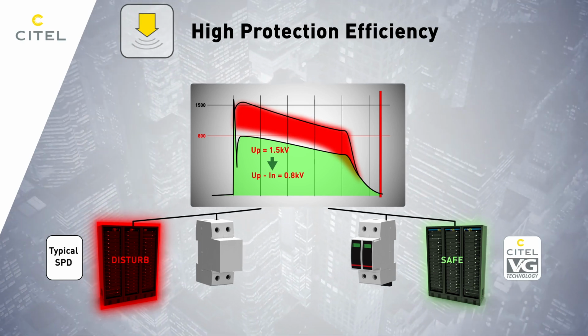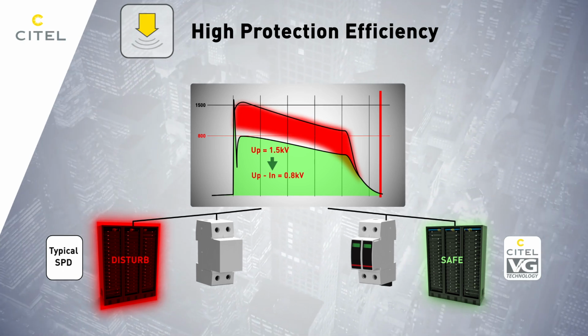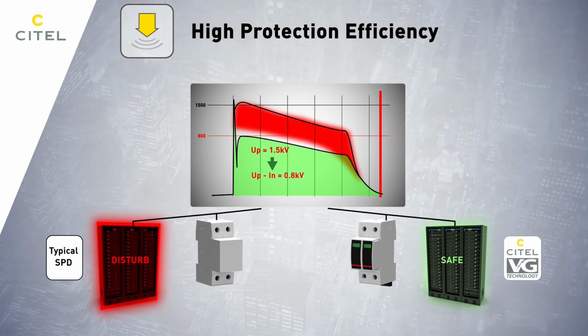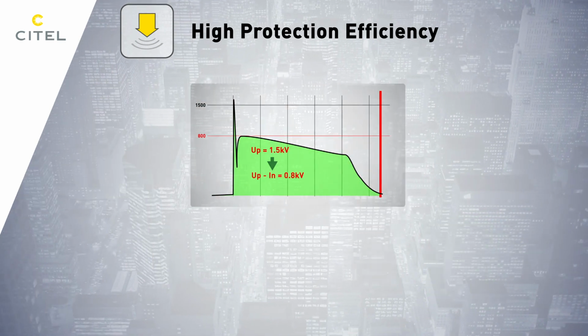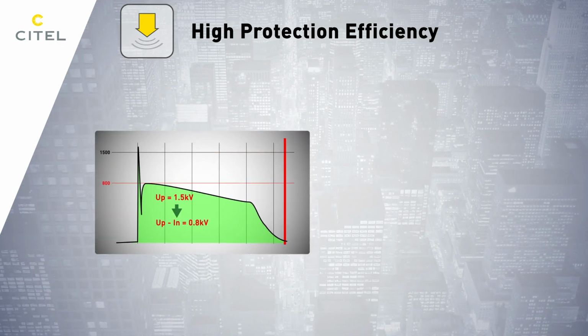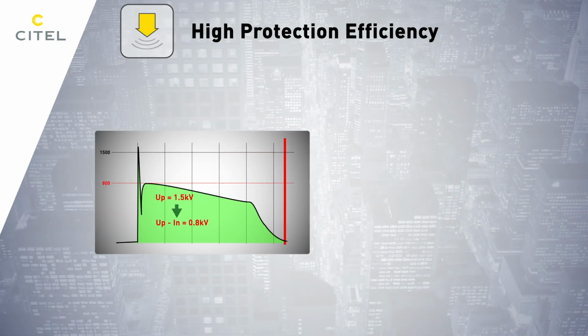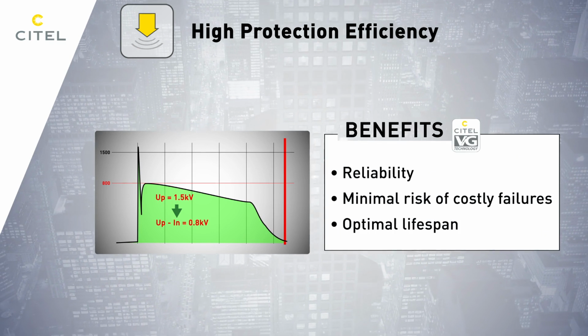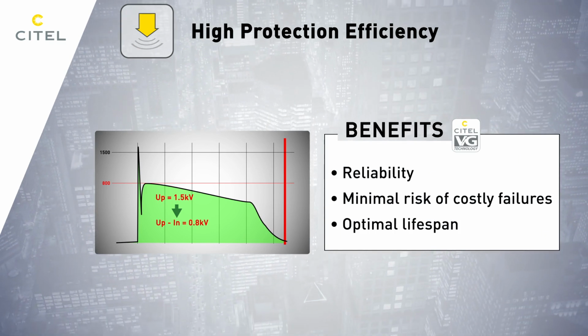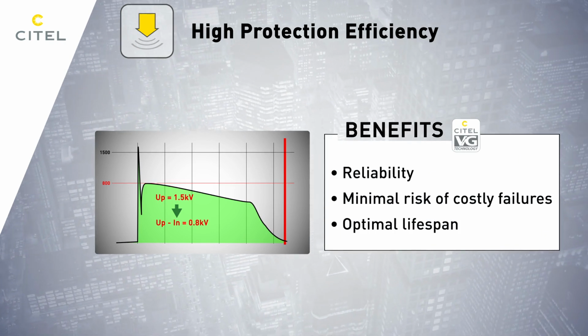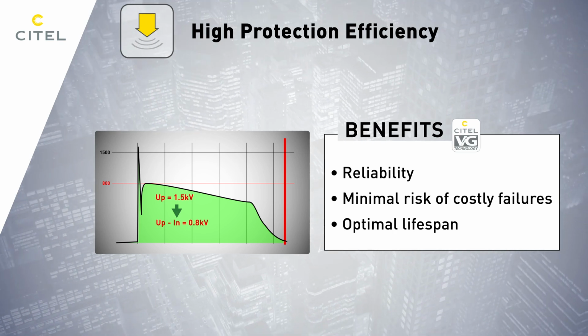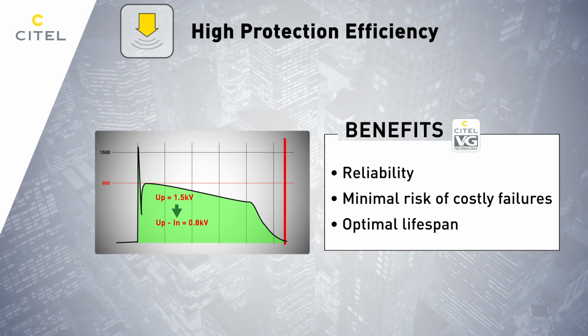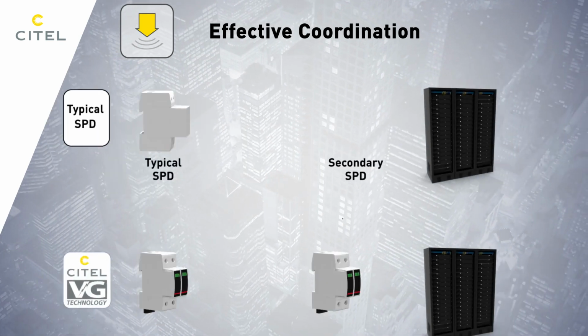UP, or voltage protection level, is the maximum voltage that reaches the protected equipment during a surge event. A good SPD must ensure a low UP to effectively safeguard devices. VG strikes the perfect balance: long-term reliability, a minimal risk of costly failures, and optimal lifespan for even the most sensitive electronics in multi-stage surge protection systems.